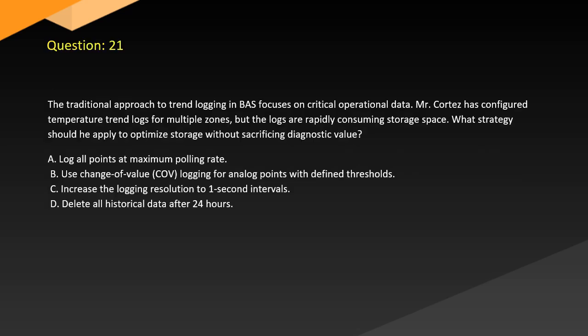Question 21. The traditional approach to trend logging in BAS focuses on critical operational data. Cortez has configured temperature trend logs for multiple zones, but the logs are rapidly consuming storage space. What strategy should he apply to optimize storage without sacrificing diagnostic value? A. Log all points at maximum polling rate. B. Use change of value (COV) logging for analog points with defined thresholds. C. Increase the logging resolution to 1-second intervals. D. Delete all historical data after 24 hours.